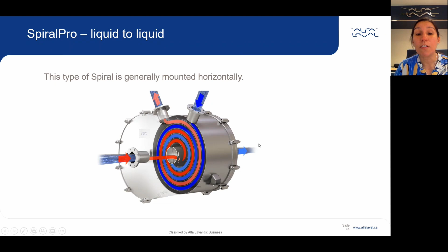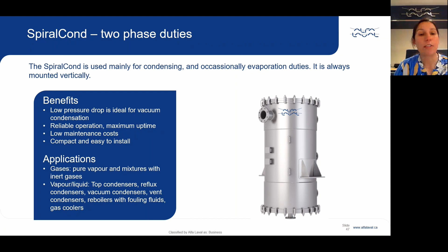Now, something that you might not be aware of is that the spiral is also very much used as a two-phase condenser, so condensing vapors, especially when very low pressure drop is required. So it is ideal for vacuum condensation, because a spiral can be designed with a very large spacing in the channel. That allows the vapor to condense with very low pressure drop.